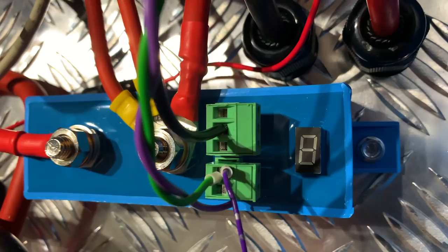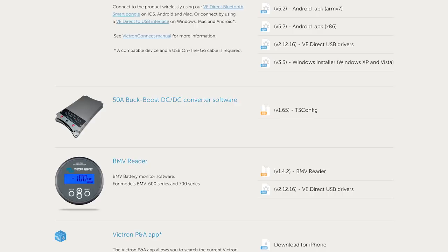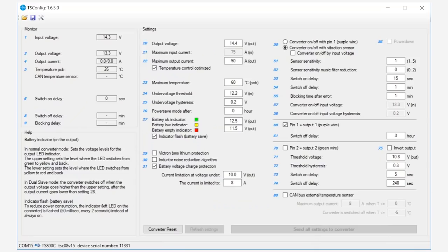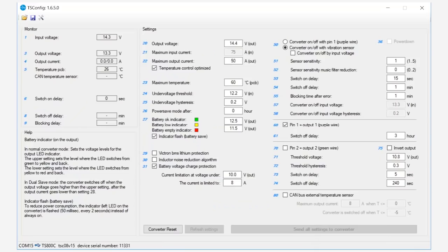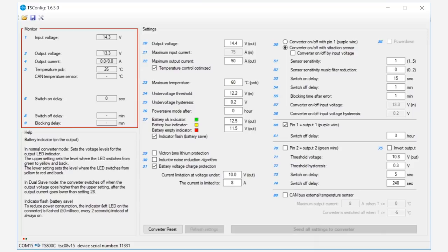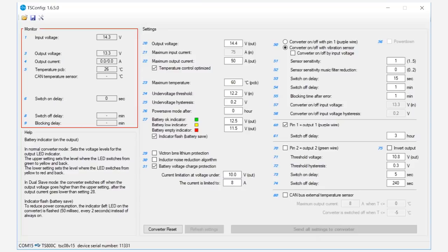To program the buck boost, the engineers downloaded the Windows operating software, TSConfig, from the Victron Energy website. This is the program's configure screen. The left panel monitors the voltages, currents, temperatures, and other settings that cannot be changed. The engineers will be changing the settings in the middle and right-hand panels for this install.